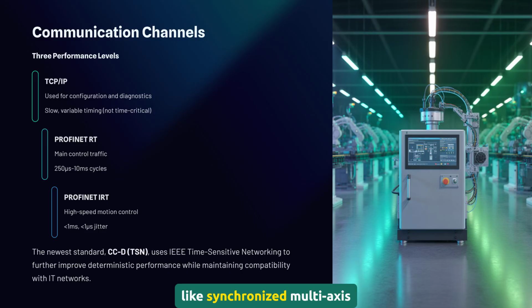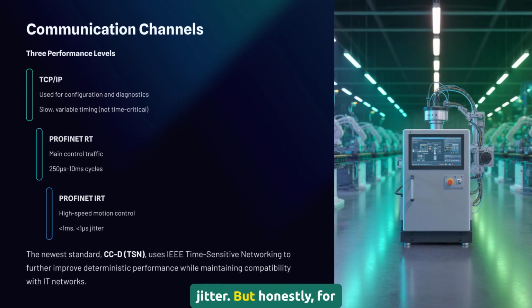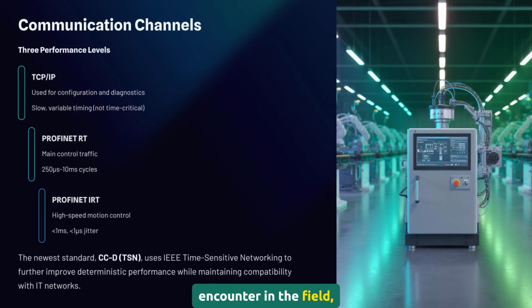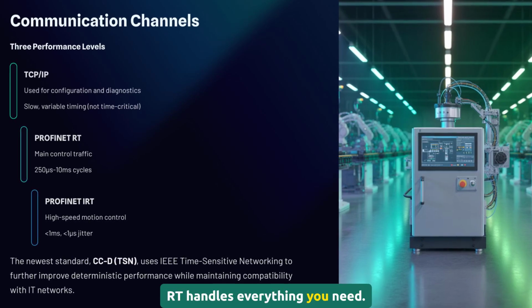Now for really demanding stuff like synchronized multi-axis robotics, there's an even faster version called IRT, Isochronous Real-Time. And the newest development is Conformance Class D, which uses TSN, time-sensitive networking. CCD achieves the same high performance as IRT, but uses standardized IEEE technologies instead of proprietary hardware. The big advantage is that TSN enables truly converged networks, where your control traffic, IT data, and even video streams can all share the same infrastructure with guaranteed performance. These give you cycle times down to microseconds with virtually no jitter. But honestly, for 95% of what you'll encounter in the field, regular PROFINET RT handles everything you need.